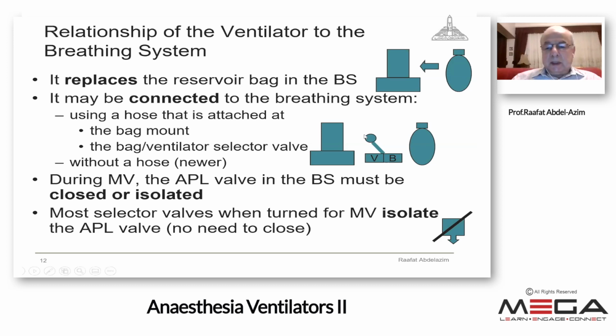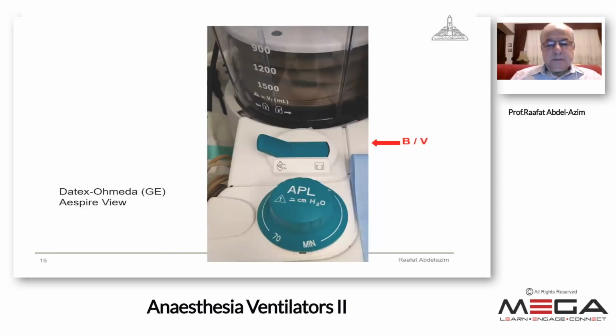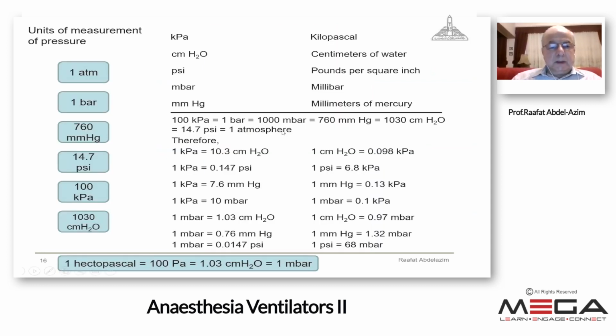In all conditions, the APL valve and the bag are isolated or should be closed in older versions. So don't worry about the APL valve and the reservoir bag after starting mechanical ventilation. This one I didn't mention before, but everybody knows that the units of measurement of pressure are in different forms. And we have to know what is 1 atmosphere. That equals 1 bar and equals 760 millimeters mercury, 14.7 psi, 100 kilopascal, or 1030 centimeters water. Because in different areas, we use different units of measurement, but the standard unit is the kilopascal, of course, as you know.